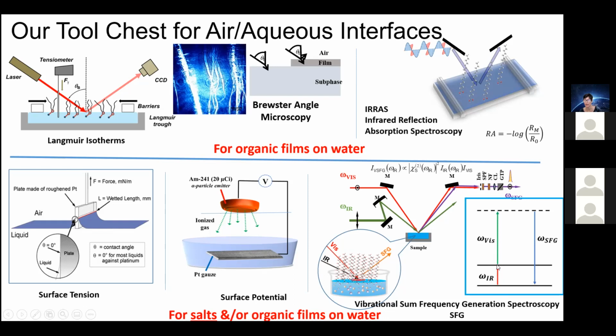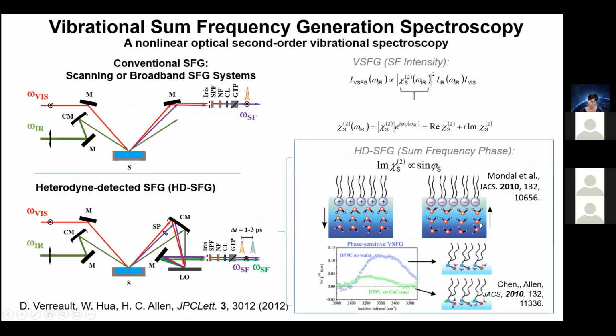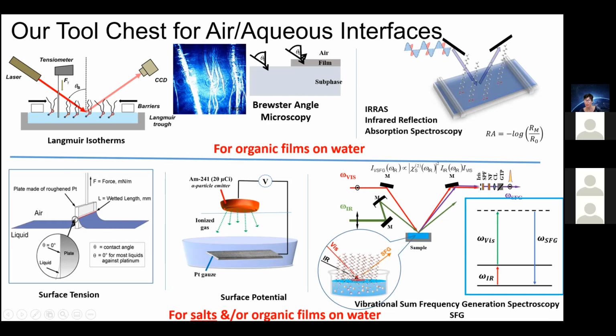We've got an infrared photon energy and a visible one, and the sum of the two frequencies is a little bit shorter in wavelength than the incident 800 nanometer. So it's anywhere from 600, and typically I think 650 to 750, in the wavelength region that we look at. And so we capture that beam with a set of optics. It's the same wavelength that an anti-Stokes Raman would be, and then capture it with a monochromator and a liquid nitrogen cooled CCD array.